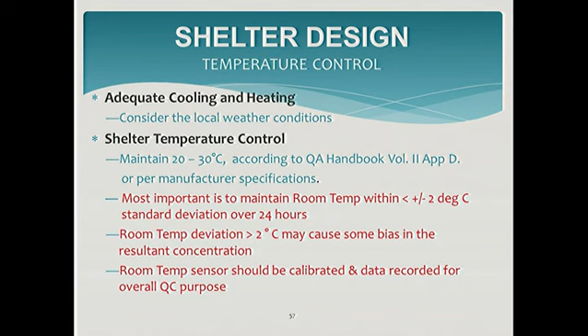Okay. So a while back, Met One acknowledged that a room temperature swing greater than 2 degrees increased the uncertainty of the PM measurements by up to 2 micrograms. The BAMs experience some negative numbers if concentrations are very low. This is due to moisture condensation and evaporation effects. Also, these fluctuations in temperature will cause problems or effects on the nightly calibrations for the gases.